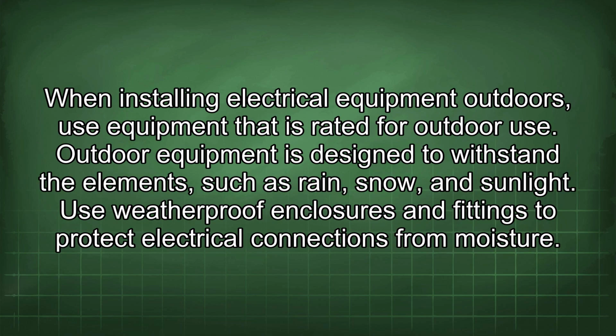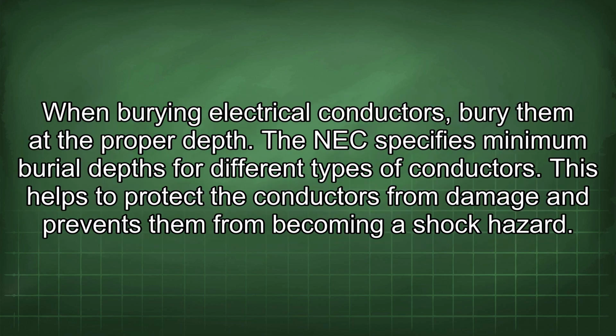When installing electrical equipment outdoors, use equipment that is rated for outdoor use. Outdoor equipment is designed to withstand the elements such as rain, snow, and sunlight. Use weatherproof enclosures and fittings to protect electrical connections from moisture. When burying electrical conductors, bury them at the proper depth. The NEC specifies minimum burial depths for different types of conductors. This helps to protect the conductors from damage and prevents them from becoming a shock hazard.